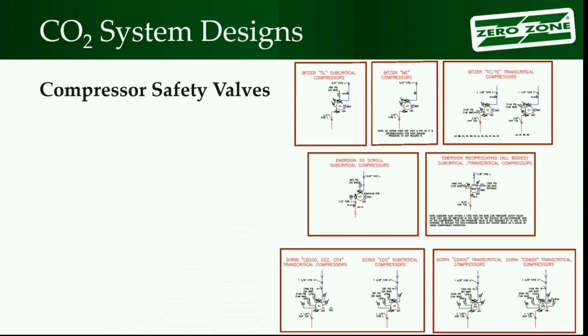Turns out compressors are probably generally your lowest designed pressure component in the system. You know, they'll be 350, I'm sorry, not 350, 435, 500. The rest of the system's 650. Compressors on the boosters tend to be the lowest pressure design in the system. So you could easily get above Bitzer 435, so that's why that safety valve's there to prevent that.